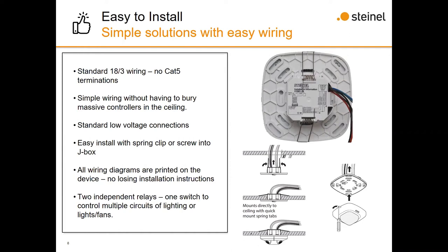So then people start doing their own terminations. But if you've ever done Cat 5 terminations, you've got 8 small terminations to do on either end of the cable, giving you 8 opportunities to make a mistake. During commissioning, we hear a lot of horror stories about the number of re-terminations a commissioning agent has to do. So the good news is our standalone uses simple 18/3 wiring, very easy low voltage wiring.